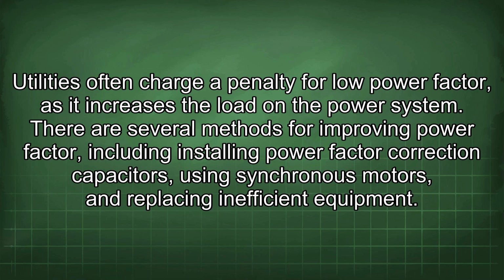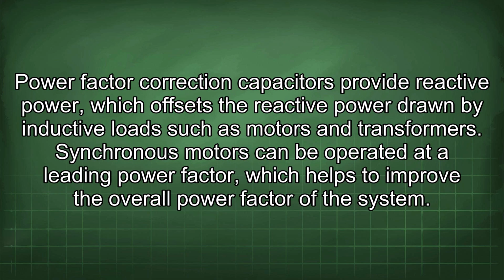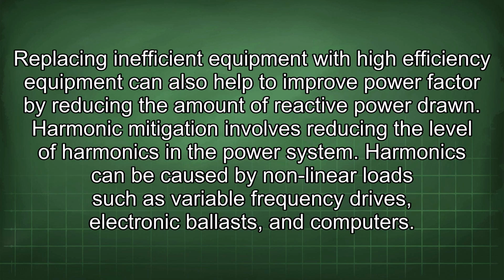There are several methods for improving power factor, including installing power factor correction capacitors, using synchronous motors, and replacing inefficient equipment. Power factor correction capacitors provide reactive power, which offsets the reactive power drawn by inductive loads such as motors and transformers. Synchronous motors can be operated at a leading power factor, which helps to improve the overall power factor of the system.